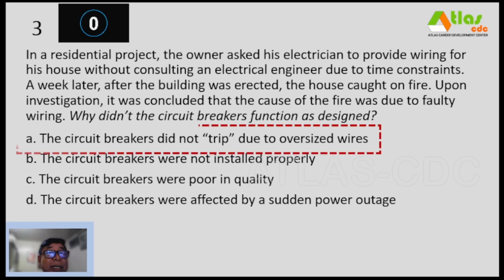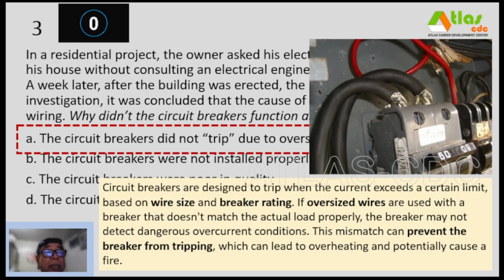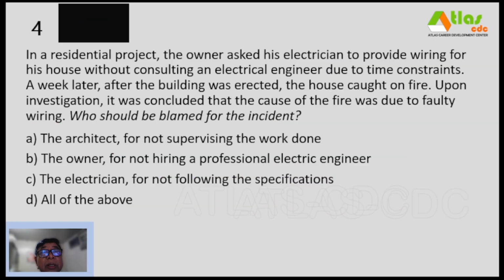And our correct answer is letter A. The circuit breakers did not trip due to oversized wires. So lahat ng choices is about the circuit breakers. So circuit breakers are designed to trip when the current exceeds a certain limit based on wire size and breaker rating. If oversized wires are used with a breaker that doesn't match the actual load properly, the breaker may not detect dangerous overcurrent conditions. This mismatch can prevent the breaker from tripping, which can lead to overheating and potentially cause a fire.